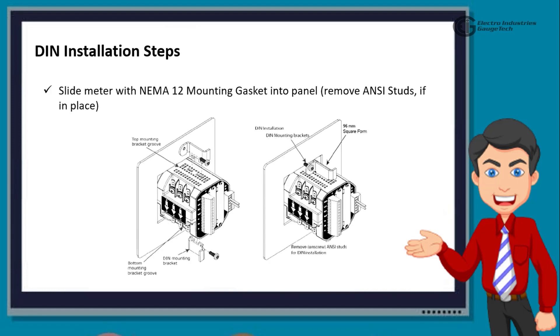After this, we have the DIN installation steps. The first step is slide meter with NEMA 12 mounting gasket into panel. Remove ANSI studs if in place. Then, from back of panel, slide down mounting brackets into grooves in top and bottom of meter housing. Snap into place. Lastly, secure meter to panel by using a 2 Phillips screwdriver to tighten the screw on each of the two mounting brackets. Do not over-tighten. The maximum installation torque is 0.4 Newton meter.